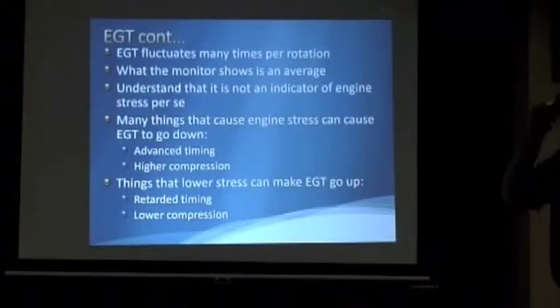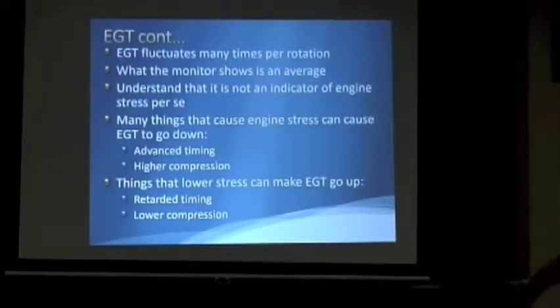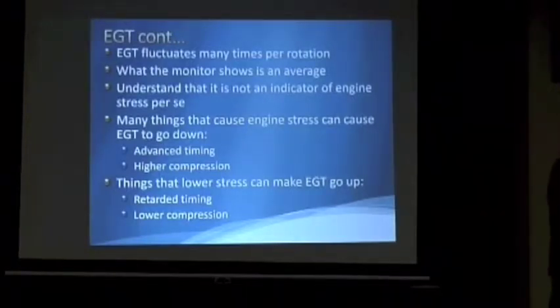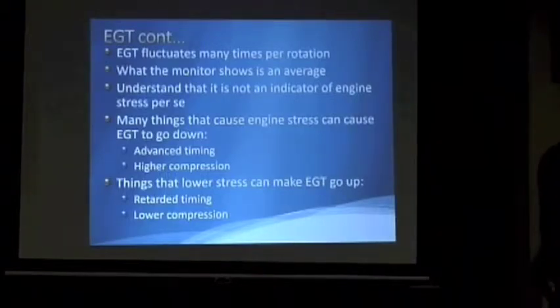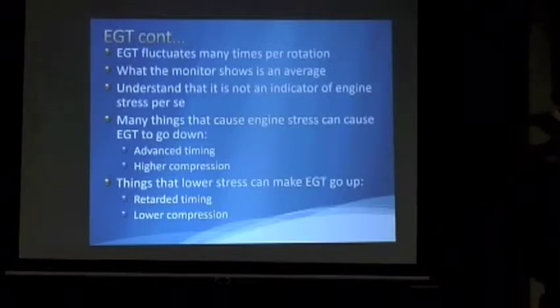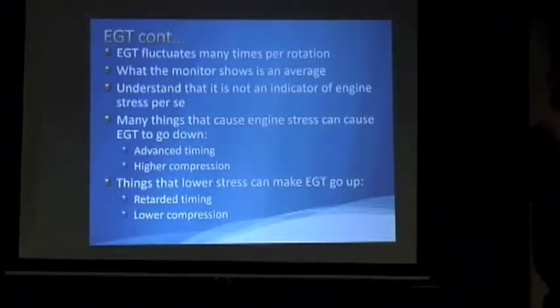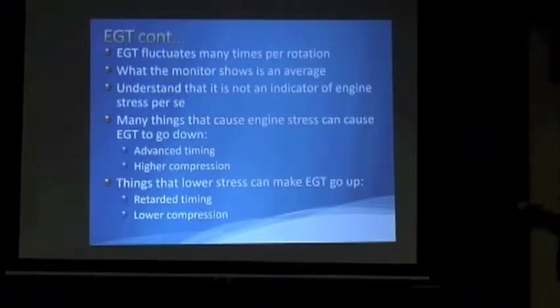So it fluctuates many times per rotation, and what the monitor shows is an average. It's not necessarily an indicator of specific engine stress, because it's an average - you could have a very high peak and a very low one, and the average will come out the same as a lower peak and a higher low, so you'd end up with the same average.